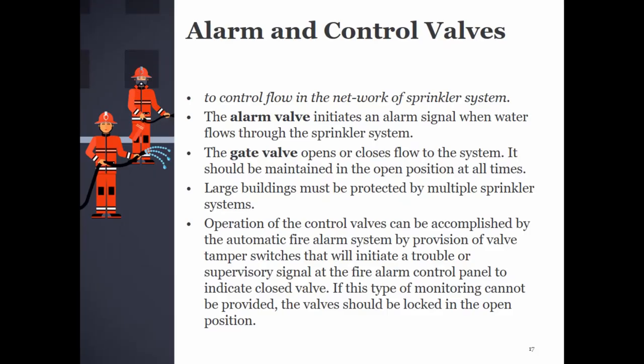Alarm and control valves: An alarm valve and gate valve control flow in the network of the sprinkler system. The alarm valve initiates an alarm signal when water flows through the sprinkler system. The gate valve opens or closes flow to the system and should be maintained in the open position at all times. Large buildings must be protected by multiple sprinkler systems, each having an alarm valve and gate valve. Operation of the control valves can be accomplished by the automatic fire alarm system; valve tamper switches initiate a trouble signal at the fire alarm control panel to indicate a closed valve.